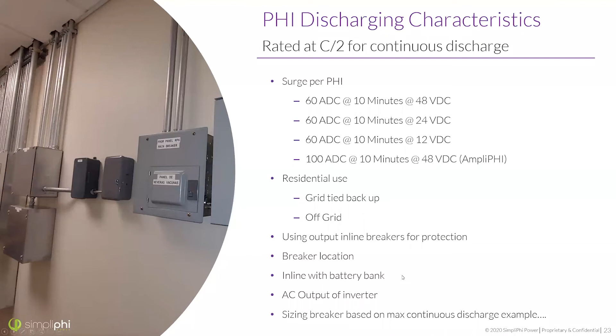So if you've got, let's say, a 3.8 kilowatt hour battery at 48 volts, and you've got 2 of those, you know your max discharge is 37.5 amps per battery. So the 2 of those can handle 75 amps DC. Max continuous discharge is the entire bank. So you'd probably go down a little bit to a 60 amp breaker.